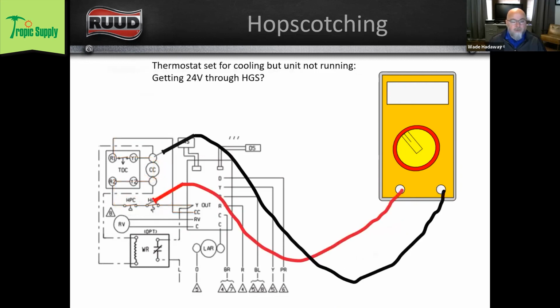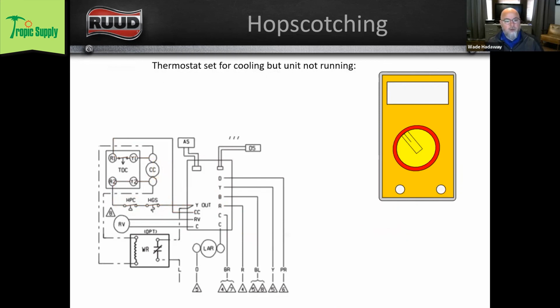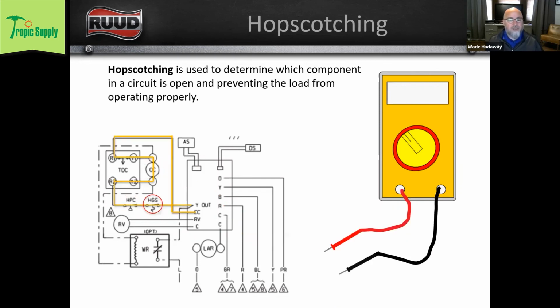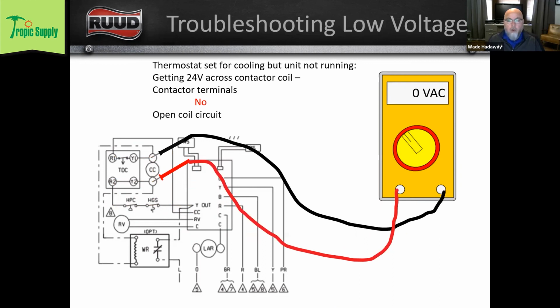So are we getting 24 volts? We know when we checked across our contactor coil, we didn't have voltage sitting there. So what that tells me is there's no electrical potential at my coil. So I've got an issue somewhere with the power before it gets to my contactor coil.